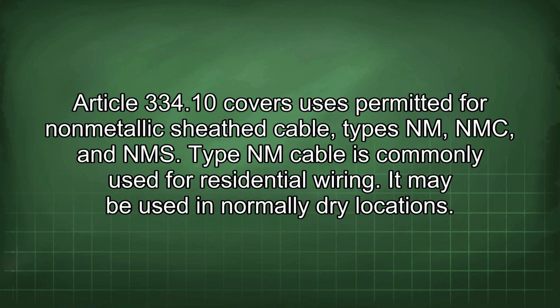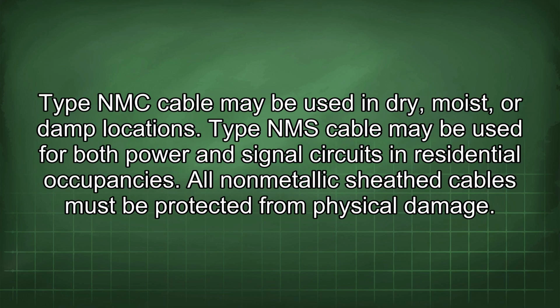Article 334.10 covers uses permitted for non-metallic sheath cable, types NM, NMC, and NMS. Type NM cable is commonly used for residential wiring. It may be used in normally dry locations. Type NMC cable may be used in dry, moist, or damp locations. Type NMS cable may be used for both power and signal circuits in residential occupancies. All non-metallic sheath cables must be protected from physical damage.